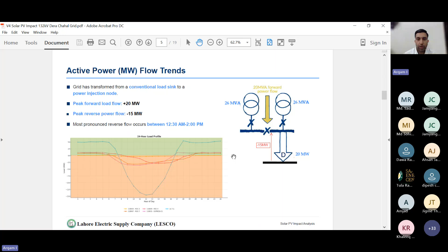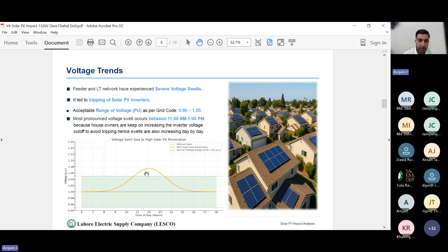So reverse power flow is one of the challenges. The other big challenge is that during the peak production of solar energy, we have massive overvoltages. The normal criterion in the grid code is plus or minus 5% of the standard value, but now we are facing almost 10% overvoltage above the standard limits. Also, as we have inverter-based generation, they generate electricity at unity power factor, or 0.95 power factor in the lagging state.